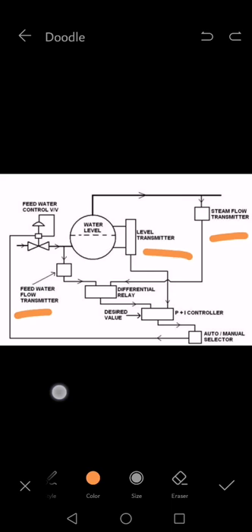There's also on-off control. On-off control basically works like this: let's say when the boiler comes to low level, if 100 millimeters of water column is normal, and it drops to 50 millimeters, the pump starts, and when it reaches 150 millimeters, it stops. On-off control can work, but in that system pumps frequently start and stop.